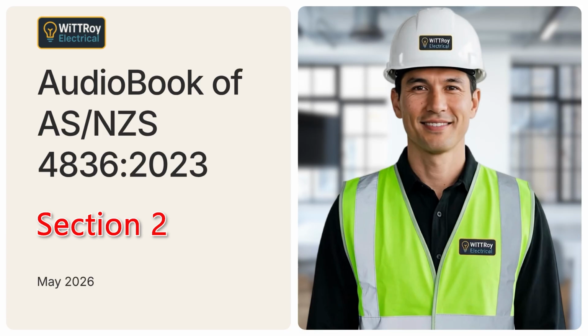Clause 2.3.7 Work Zone. Clause 2.3.7 explains work zones. If any person is required to work within 3 meters of energized exposed conductors or parts, a competent person must identify suitable risk treatments. In simple terms, when work is within 3 meters of exposed energized parts, the work must be treated as electrically risky and proper controls must be selected.